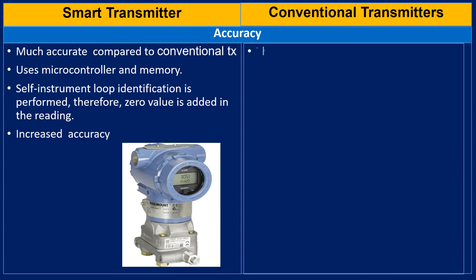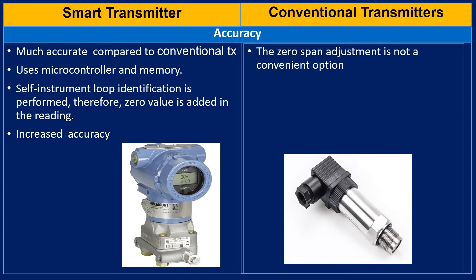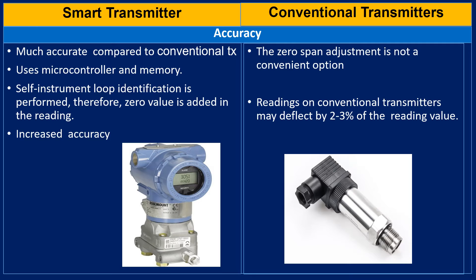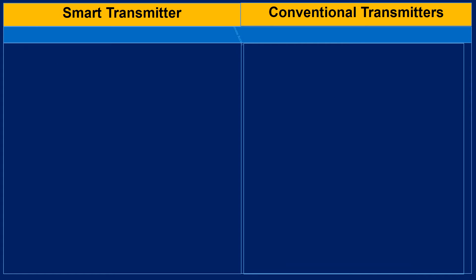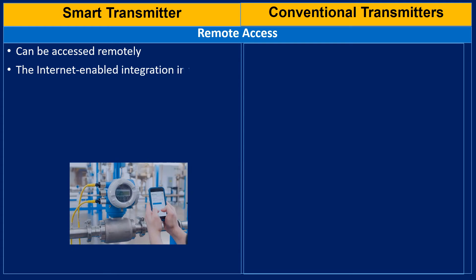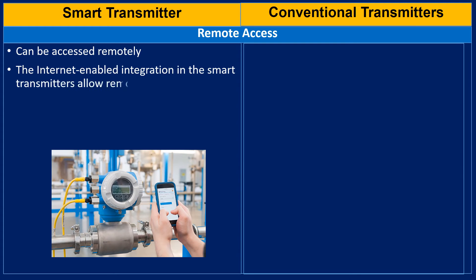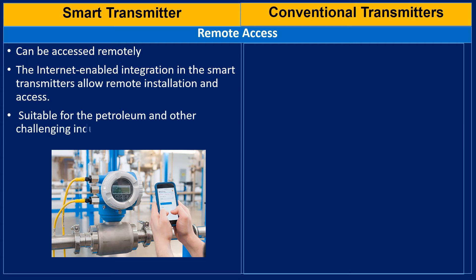In conventional transmitters, zero span adjustment is not a convenient option due to their analog nature. Therefore, the reading of conventional transmitters may deflect by 2 to 3% of the reading value. Smart transmitters can be accessed remotely — internet-enabled integration allows remote installation and access, making them suitable for petroleum and other challenging industries. Conventional transmitters cannot be accessed remotely.